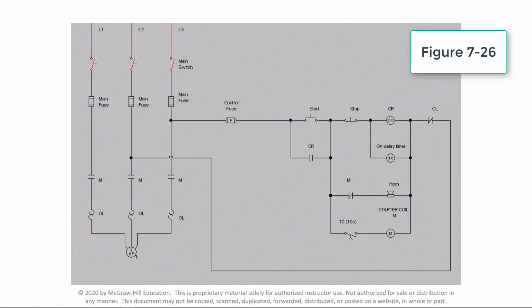This video demonstrates the operation of a conveyor motor warning signal circuit with an on-delay timer. Coil CR is energized when the start push button is momentarily actuated. As a result, contact CR closes to seal in the CR coil and energize timer coil TD and establish the circuit to sound the horn. After a 10-second time delay, normally open timer contact TD closes to energize the motor starter coil M to start the motor and turn off the horn.